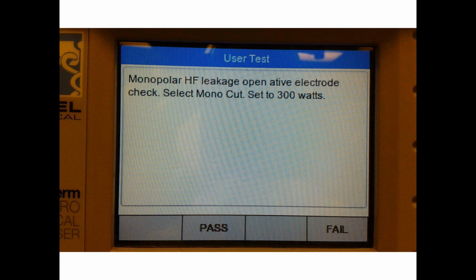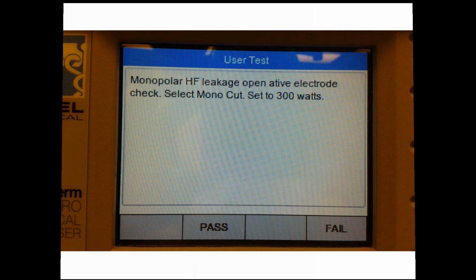So this would be an example of a monopolar test, open active electrode, monopolar cut, and we're setting the generator to 300 watts. This is a little snapshot of one of our auto test sequences where we've tried to include as much information from the service manual as possible so that you don't necessarily have to have a service manual in front of you as you're conducting your testing. Just trying to make it as simple and easy as possible.